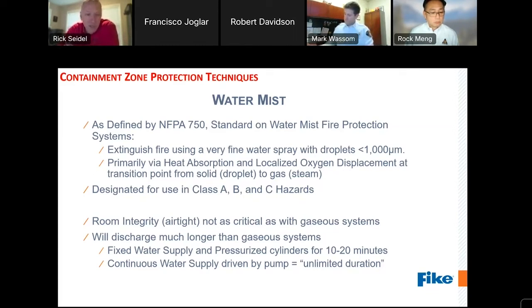Most gaseous systems discharge for 10 seconds. Fixed water supply and pressurized cylinders, self-contained water mist systems, if you will, can typically provide 10 to 20 minutes duration and protection. And lower pressure, continuous water supply systems driven by a pump can potentially give you an unlimited duration of discharge into the hazard.